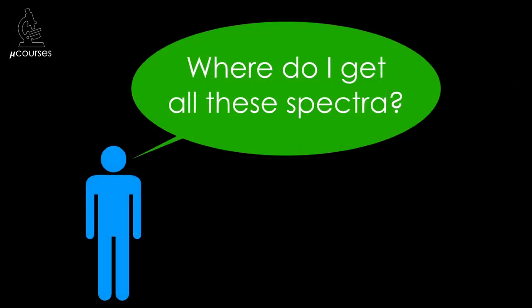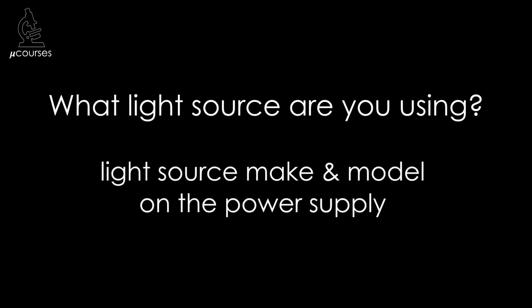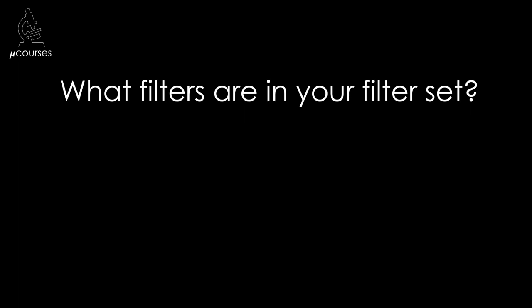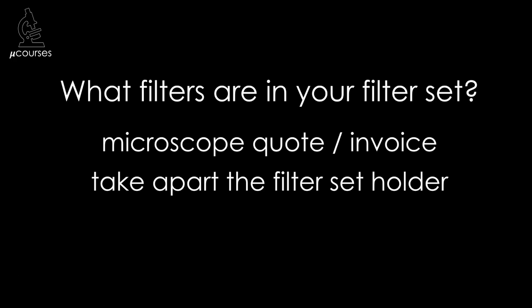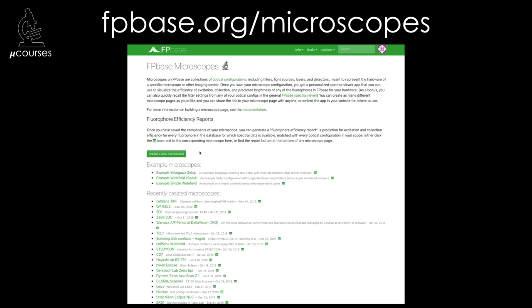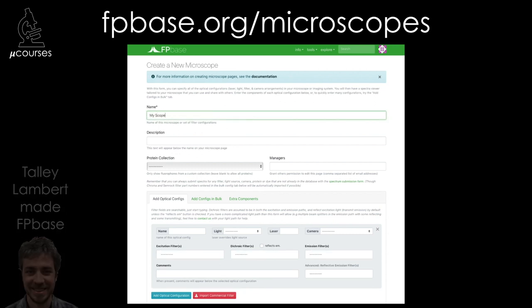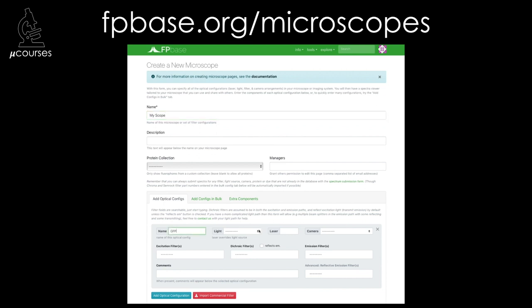So how can you go about finding this information for your microscope? First, look at the power supply box for your light source and get the make and model. Then figure out what filter set you have — check the original microscope quote or invoice, or take apart the filter set holder, or ask your commercial rep for help. Then head over to fpbase.org/microscopes. On this website, you can build your microscope, input the light source and filter sets, and generate a spectra viewer you can save or embed in your lab website. fpbase contains a database of fluorophore spectra to compare to your microscope, light source, and filters. Please always choose your filter set carefully.